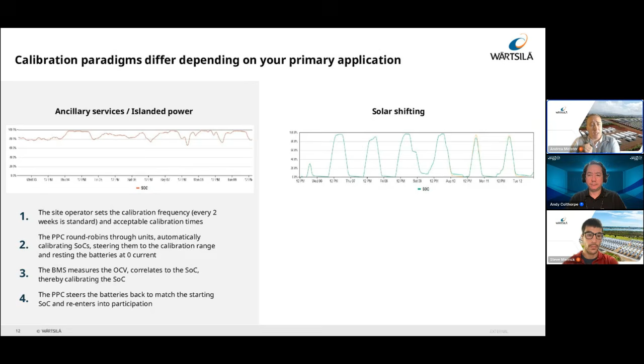Calibration paradigms will differ somewhat depending on the primary application of that BESS. With the Wärtsilä GEMS PPC, we are able to stack operations, so a site can perform both solar shifting and ancillary services, but we do find that sites tend to divide themselves based on what the market needs. Let's talk first about ancillary services, or a site where most of the time a battery is between 40 to 80% state of charge. In that paradigm, a site operator would set the calibration frequency, and the GEMS PPC's role is to round robin through units, bringing them down to the calibration range, resting them, calibrating that SoC, measuring it with the BMS, and then steering it back up into participation.